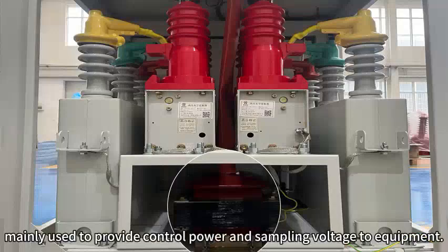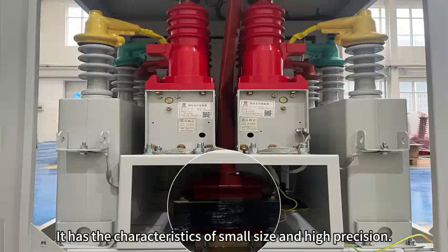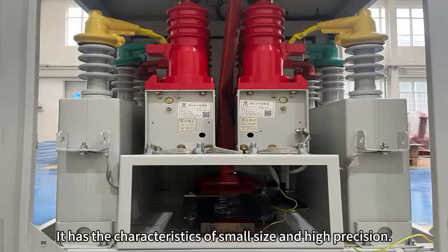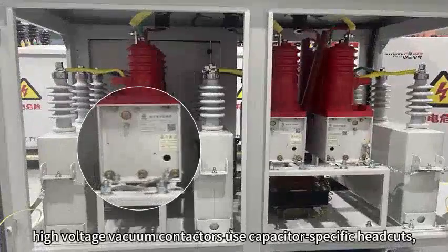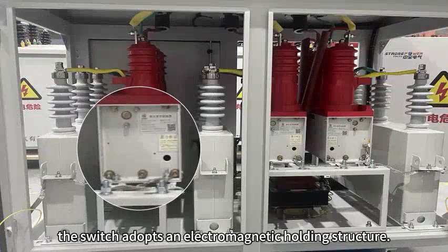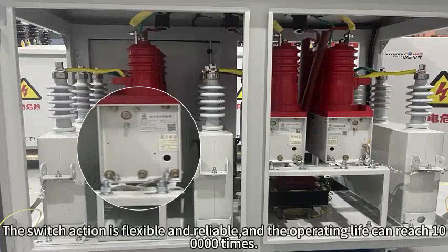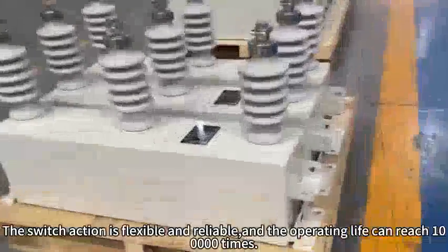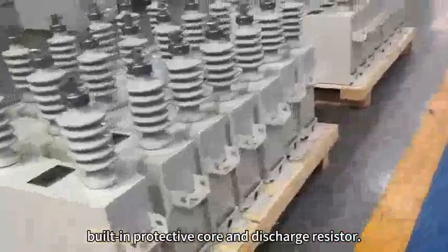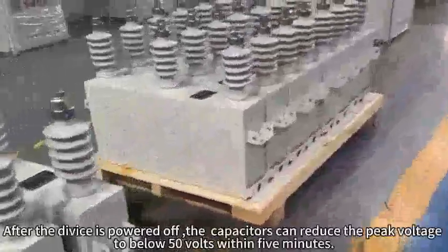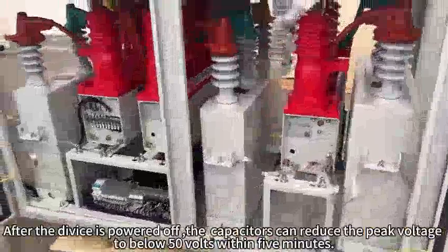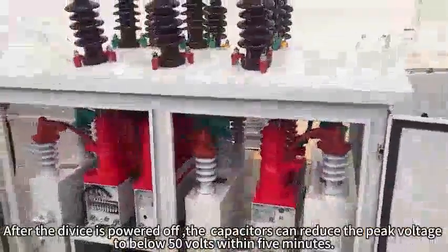The power PT is mainly used to provide control power and sampling voltage to the equipment. It has the characteristics of small size and high precision. Secondly, the high voltage vacuum contactor uses a capacitor-specific switch. The switch adopts an electromagnetic holding structure. The switch action is flexible and reliable, and the operating life can reach 100,000 times. The high voltage shunt capacitor adopts an all-film dielectric, with a built-in protective core and discharge resistor. After the device is powered off, the capacitors can reduce the peak voltage to below 50 volts within 5 minutes.